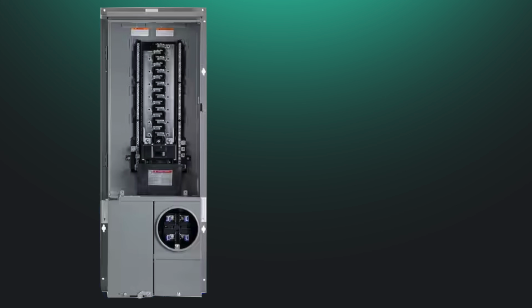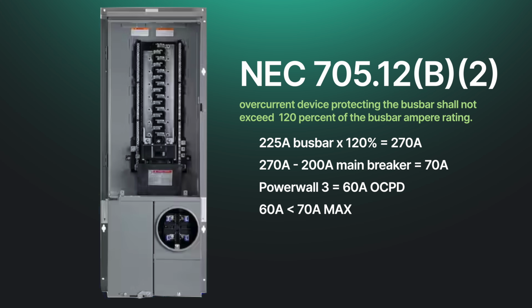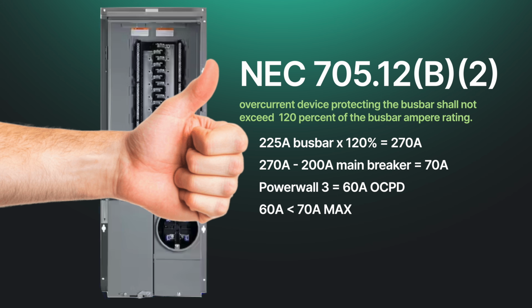A common upgrade would be replacing the existing panel with one that has a 225 amp busbar while retaining the same 200 amp main breaker. As you can imagine, the calculations have changed. 225 amps multiplied by 120% equals 270 amps. Subtract that same 200 amp main breaker and you're left with 70 amps available for solar or battery backfeed. Now the Powerwall 3's 60 amp breaker fits comfortably within the allowable limit. In simple terms, upgrading the panel increased the capacity of the busbar. The electrical system now has more room to handle electricity moving through it. This worked well for many years, but it also meant homeowners were spending thousands of dollars on electrical upgrades that were sometimes only necessary because of these code limitations.